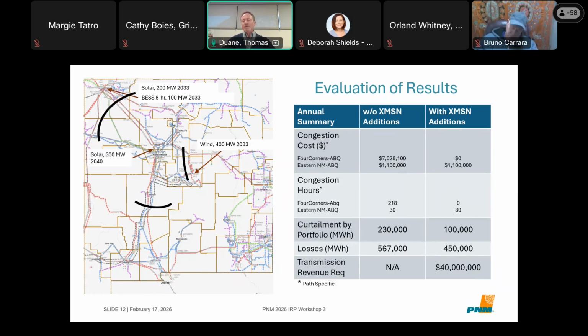The expansion did nothing to increase capacity out of eastern New Mexico, so those results are unchanged. But the effect on the curtailments that were occurring was to reduce them. There could still be reasons you'd see some curtailment, but the nodal model tells us how effectively it addressed those. Typically in this case we assumed a fairly large 345 kV transmission addition, and you'll generally see fairly big benefits in transmission losses from large capacity additions to the system.